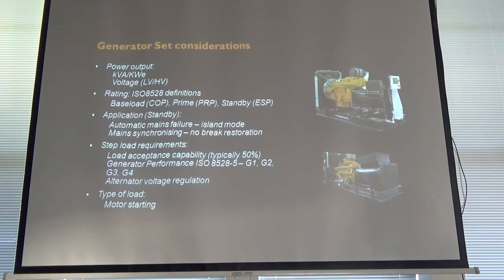The reasons behind that are the Cummins unit and the MTU units, they comply with the NFPA 110 specification, which is an American origin spec, which means for fire pumps and fire situations, basically they want to bang full load on this and have it not stall. So some of these generators really do have the legs to take the 100% load hit, but it's not recommended, but it's nice to know you've got it if you ever need it. Now that in turn relates to a higher performance capability with taking a load step.